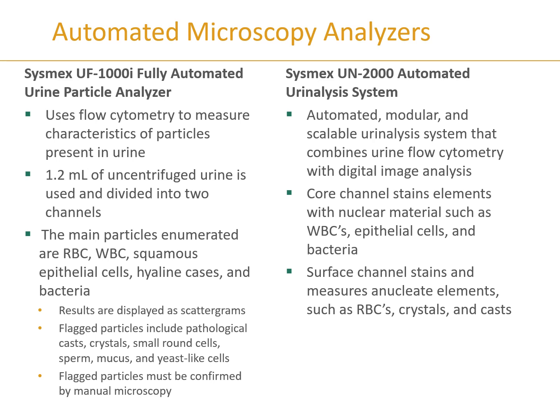Sysmex has a couple of analyzers that use flow cytometry paired with digital imaging to examine elements within the urine sample. Depending on the methodology, they categorize cells into red blood cells and white blood cells, examining nuclear material, cell contents, cell surface, and size — very similar to what automated CBC differential analyzers can do.